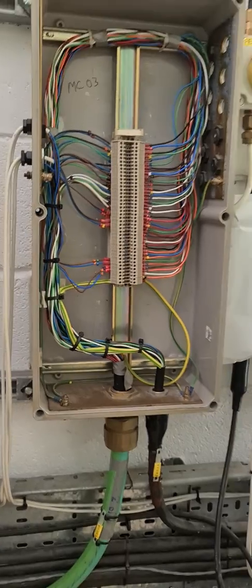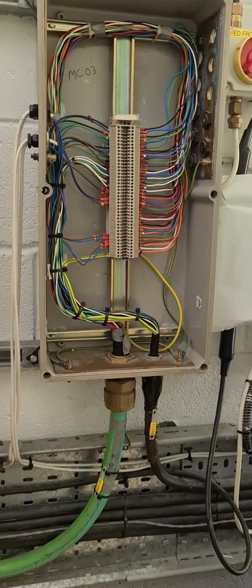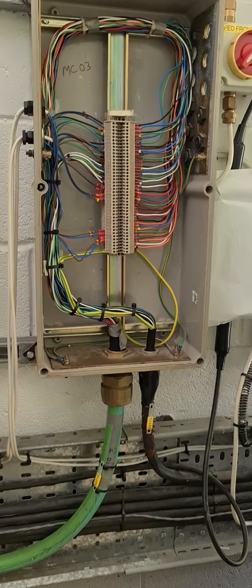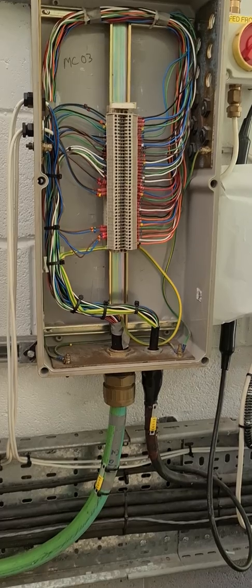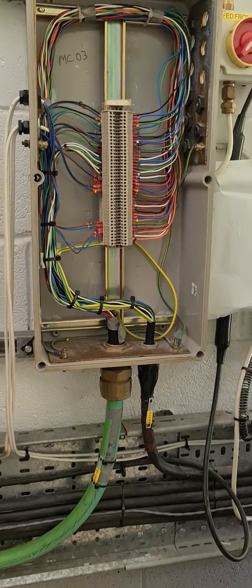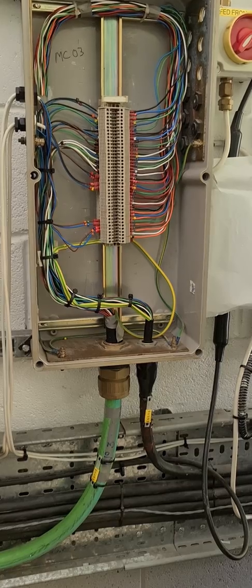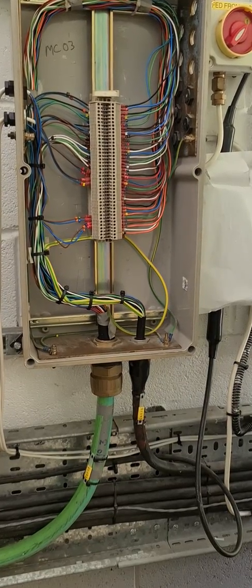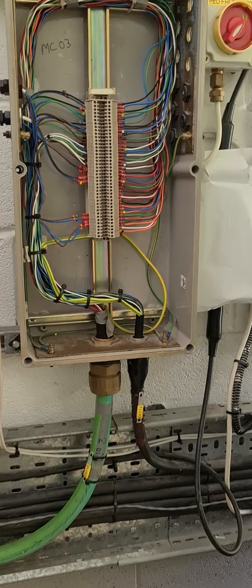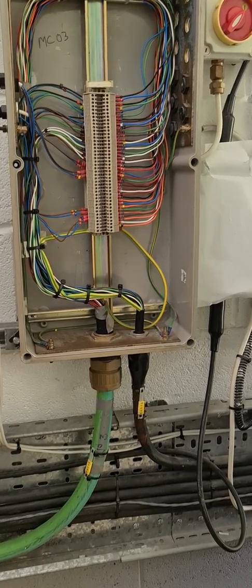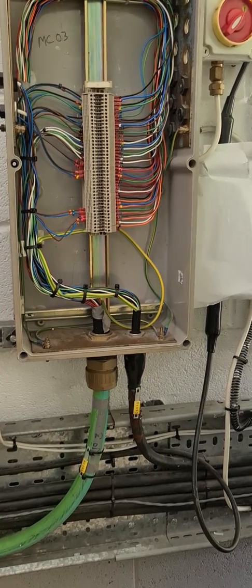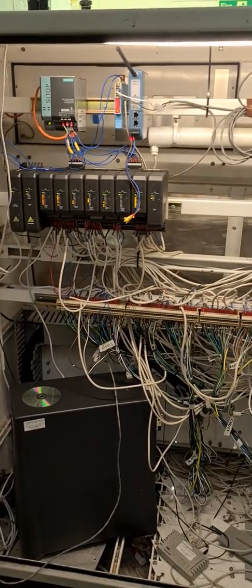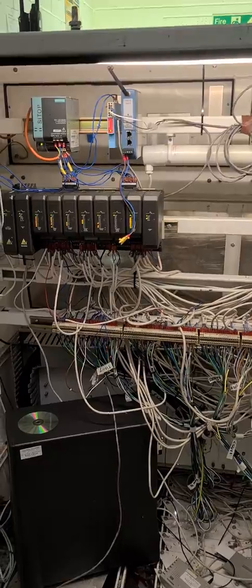The second half of this system, this is where it now comes in to the back of the control panel at 4 to 20 milliamps, incoming via the green cable, which is a 40 core multi-core cable. It then drops from 40 cores on the right hand side into just 20 core going to the left via the small multi-core cable. It is black, and that one carries 20 cables. From there it now goes to the back of the DCS system.